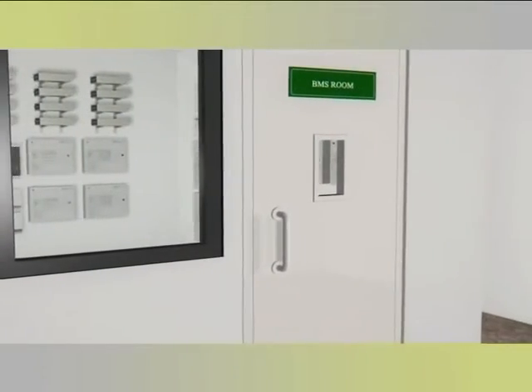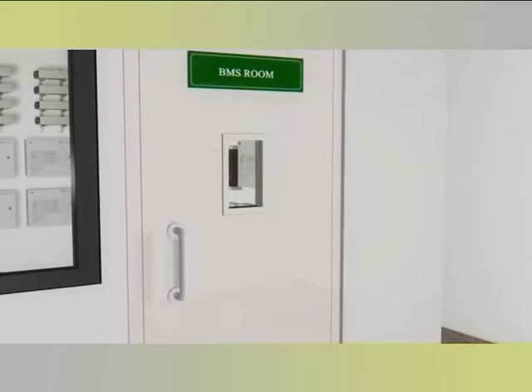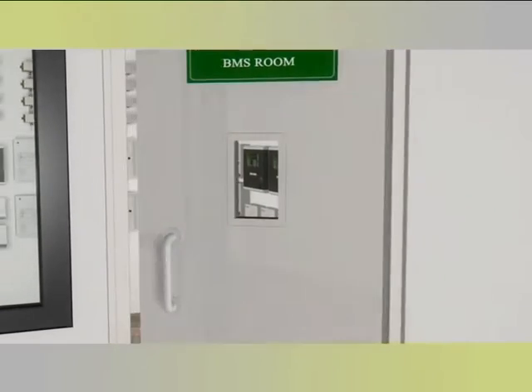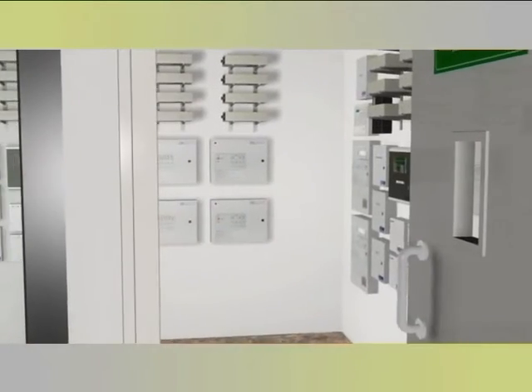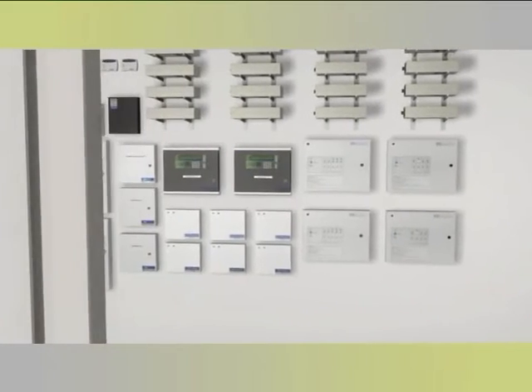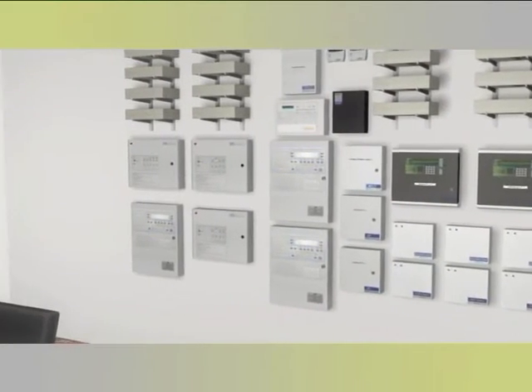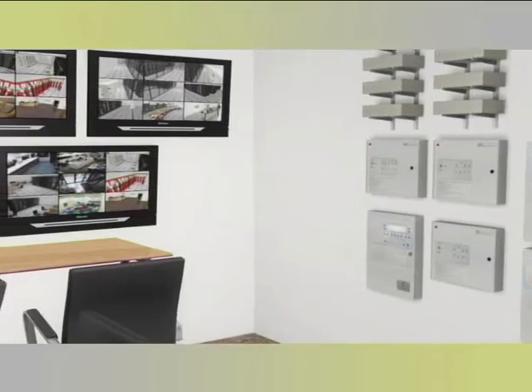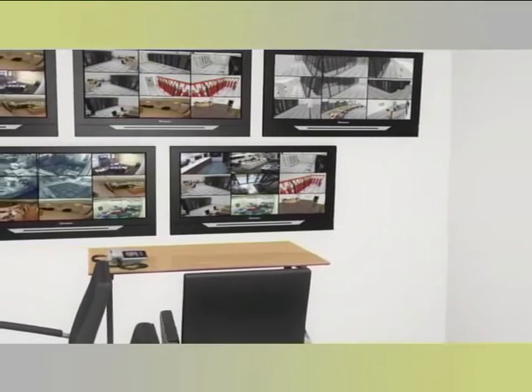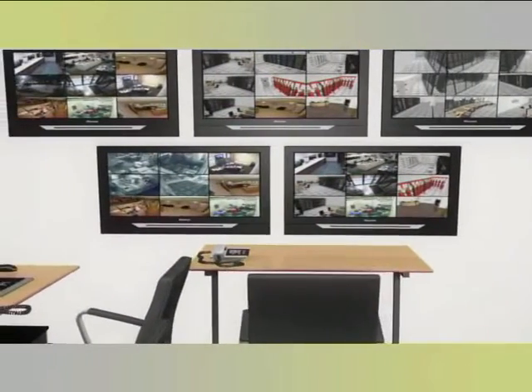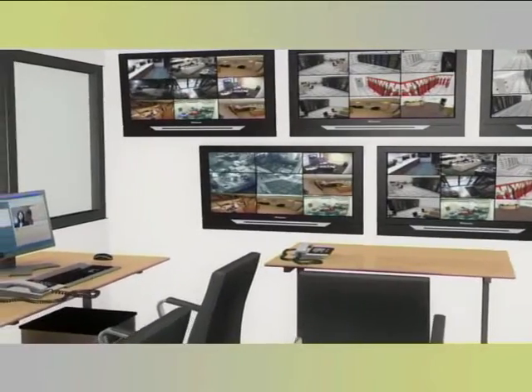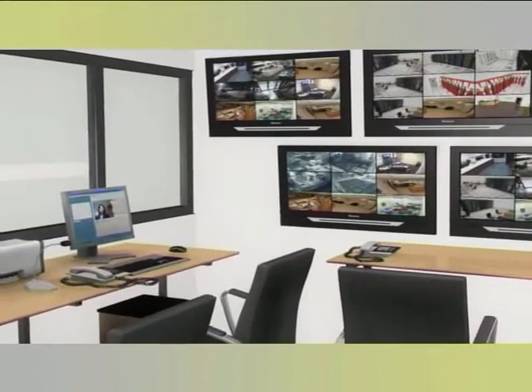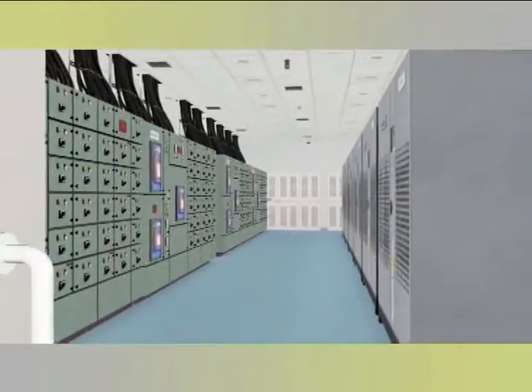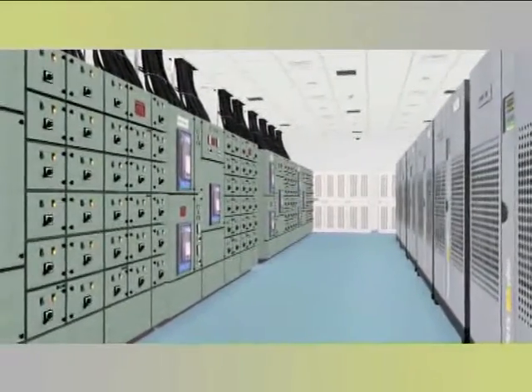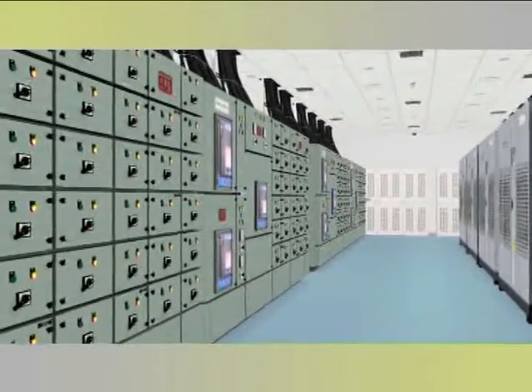In a specially designated area, a centralized console manages all components of the building management system, such as temperature, humidity, advanced fire detection and suppression systems, water leakage detection, electronic rodent control, and digital video surveillance cameras covering the center. On any instance of deviation from prescribed parameters, it raises alarms and initiates appropriate action. Power is sourced from two different substations, with a dedicated transformer bank extending feeds to the UPS systems set up in separate rooms.